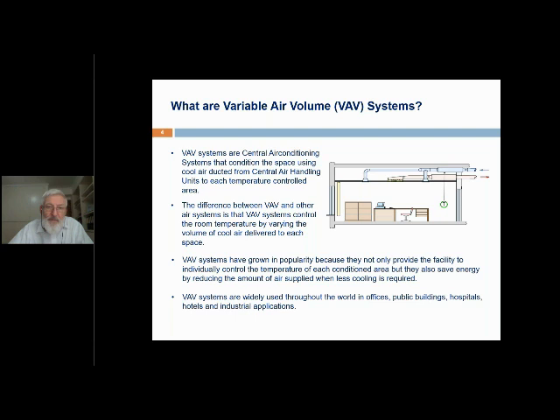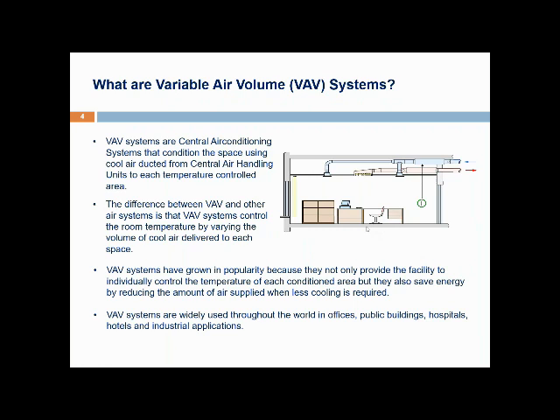VAV systems are central air conditioning systems. They condition the space using cool air conducted from central air handling units to each temperature controlled area. It's an all-air system supplying air to each space to be conditioned. The difference between VAV and other all-air systems is that VAV systems control the room temperature by varying the volume of air delivered to each space.